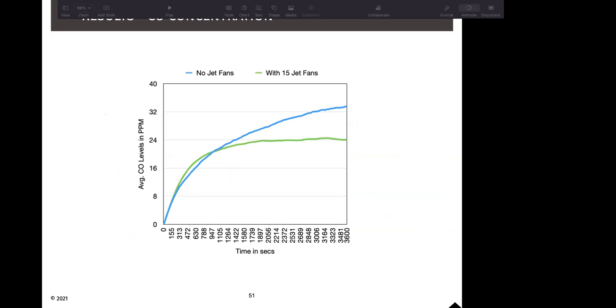And looking at the average CO level, again, we see that without jet fans, there is an increasing trend. So if left for a longer period of time, this CO will keep increasing. It hasn't reached a stable condition, which means that whatever CO is being produced is not being taken out of the system at an equivalent rate. In case of the jet fans, whatever CO is being produced is being extracted from the system and it reaches an average level of 24 ppm. So we can study with CFD what is the optimal number of jet fans, how we should be placing it around the system to get a more stabilized condition and an even extraction of CO from the system.